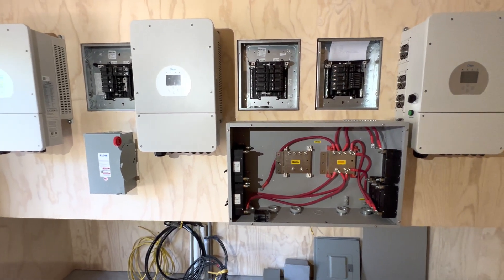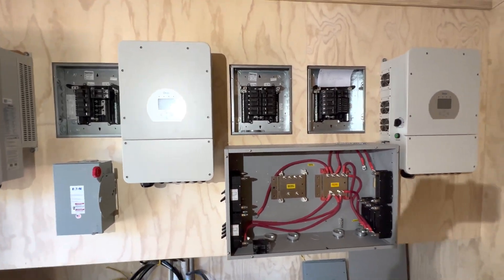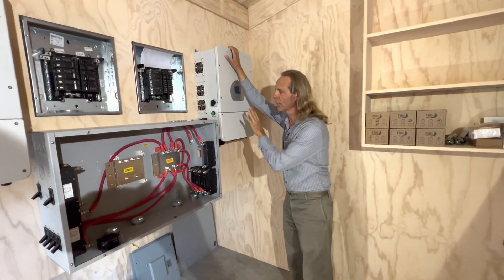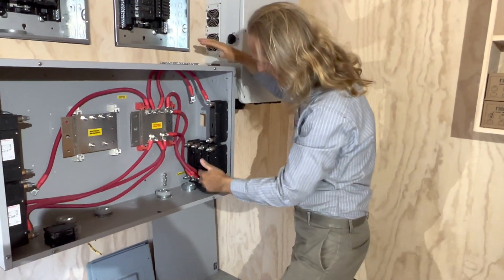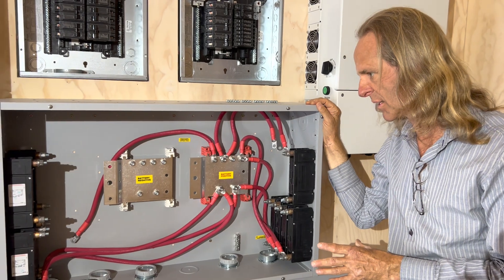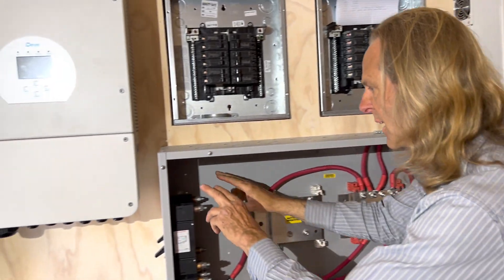The solar shed has the equipment hanging. I've got three of the Deye 8,000-watt inverters. I've got the same Midnight Solar battery combiner box with eight 175-amp breakers — one for each of the eight 14-kilowatt-hour batteries that we're building. I have three 250-amp DC breakers, one for each of the Deye inverters. So this one is for here, and these two are for there.